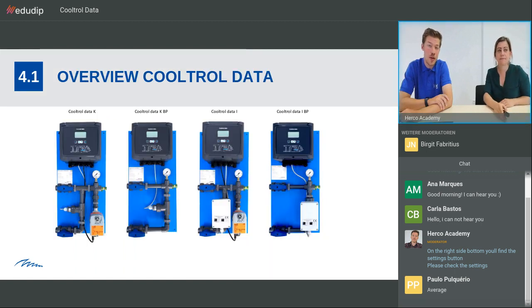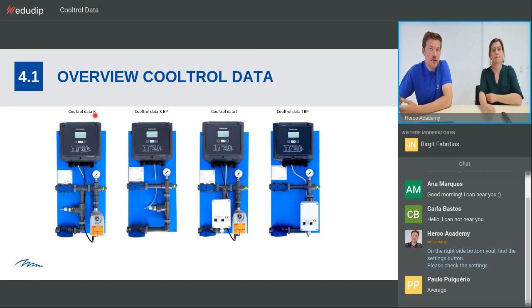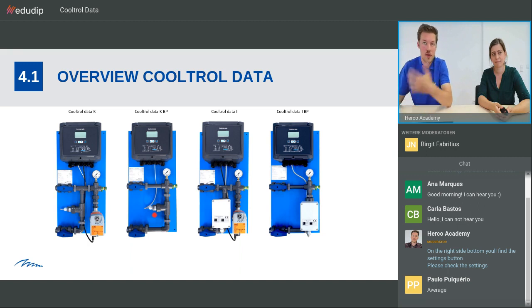All right, so here again we have an overview of the different Cooltrol data. So it's always good to know what those shortcuts mean. So it's Cooltrol data plus K. K unfortunately is German for conductive. So normally it should be C in English, but it's called K. Right, so then we have KBP for the bypass system. So you can already see here's the valve on the left side. On this one, there's no valve actually on the plate. So this is with the non-local blowdown valve, so you can install it anywhere you want. So then we have the I for inductive, so just a different measurement. You see it basically really fast.